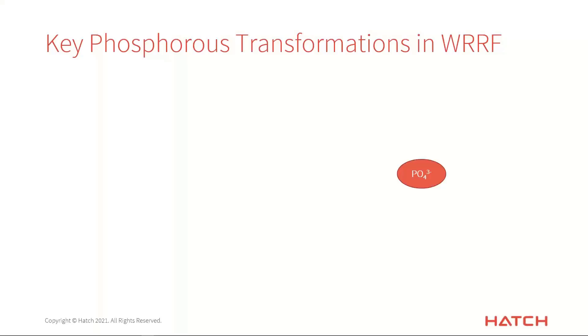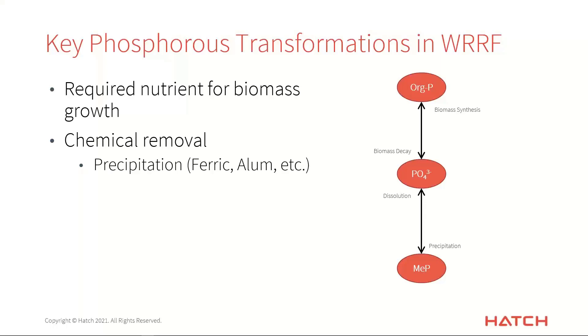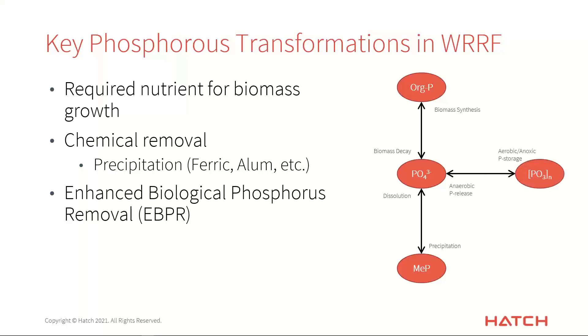We want to be able to predict soluble orthophosphate and understand how it will change over time. The key processes we need to capture in a water resource reclamation facility include: first, the required nutrient for biomass growth — this is not bioP removal, just using phosphorus as a nutrient for regular growth. We also have chemical phosphorus removal by precipitating it out with iron or aluminum. And then enhanced biological phosphorus removal, eBPR — also referred to as luxury uptake — where we grow a specific kind of biomass to accumulate as much phosphorus as possible, then waste them out into solids handling.